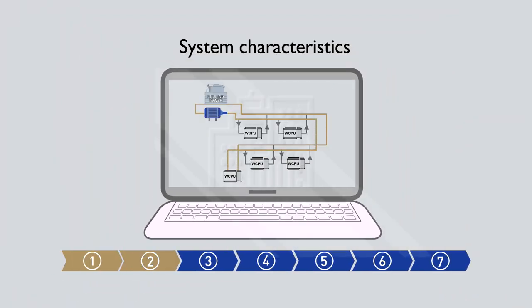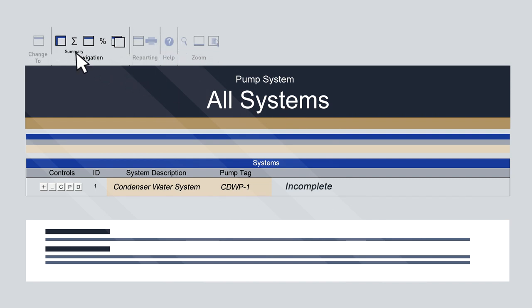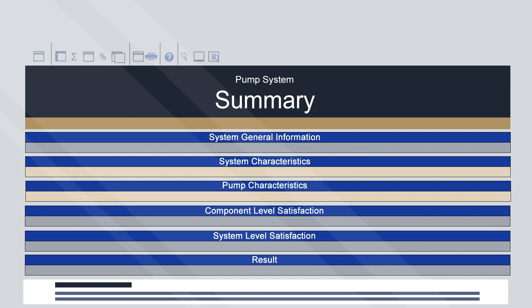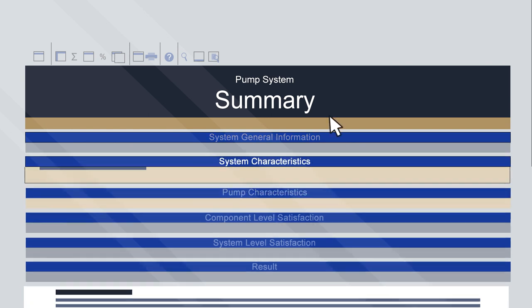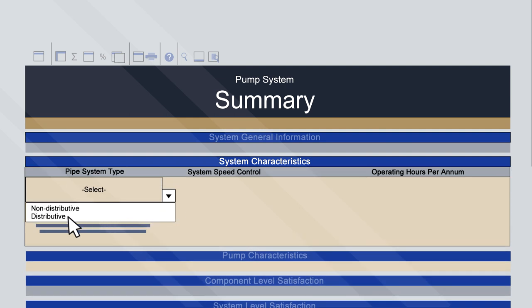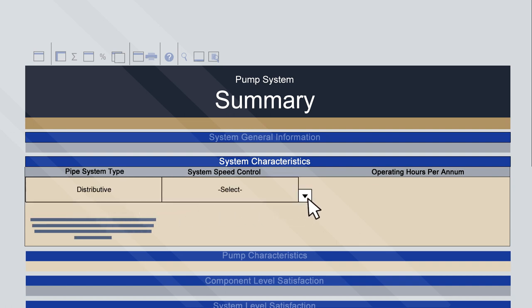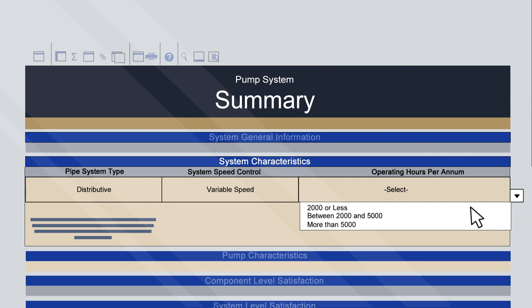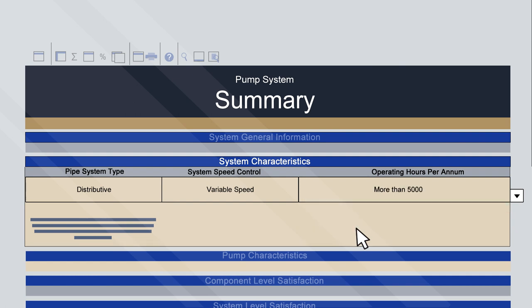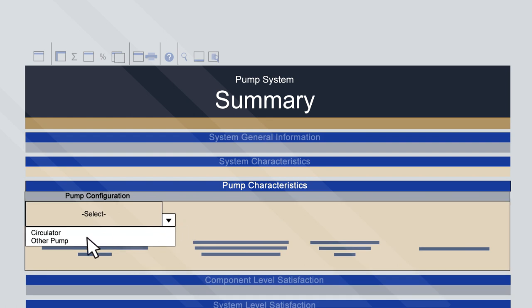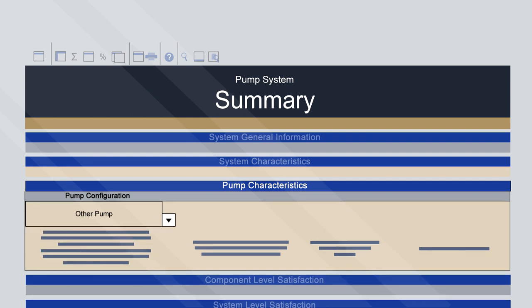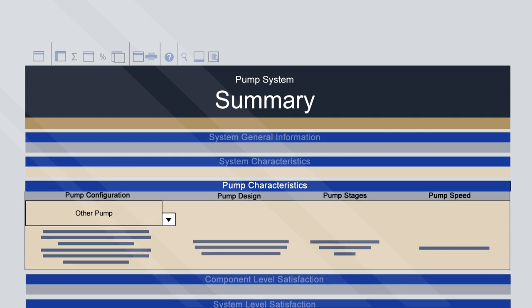Step 2: System Characteristics. Navigate to the Summary sheet using the ribbon. This sheet serves as a hub for system-wide information and results. You'll notice the project information is pre-filled from the previous step. Select the system and pump characteristics using the drop-down menus. For this example, we'll select a distributive-type pipe system with a variable pump speed and an operating time of 5,100 hours per annum, which shows as more than 5,000. Next, enter the pump configuration details. For this example, it is not a circulator pump, so is considered an other pump. The remaining pump characteristics — design, stages and speed — will be filled in later.